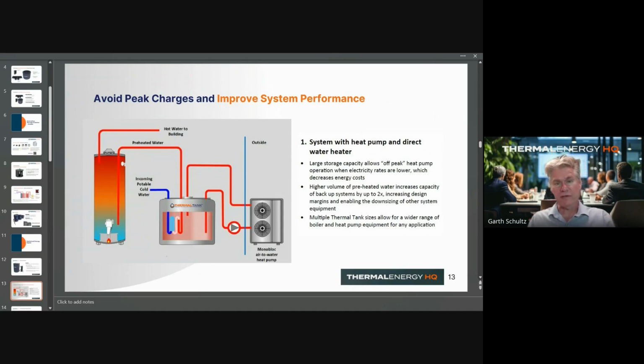And what we do is we place the thermal storage tank and the heat pump prior to that, and give that incumbent system all the preheat. And in normal operation, the incumbent system isn't going to turn on, and the thermal energy we pass on just passes through the system. But if you need a peak load to be met, then your incumbent system that you have in place will satisfy that.